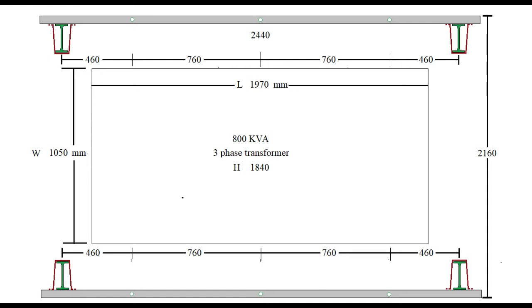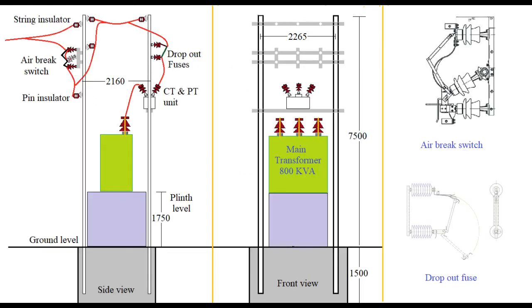Note the distance between phases and between phase and earth. This pair of poles will be fitted with lightning arresters, air break switch, pin insulators at bottom, and the conductor connected to the overhead line between the 2 pairs of poles. The live line or conductors are shown in red color that we see on screen. Conductors are shown in end view, but those are deliberately not shown in front view.